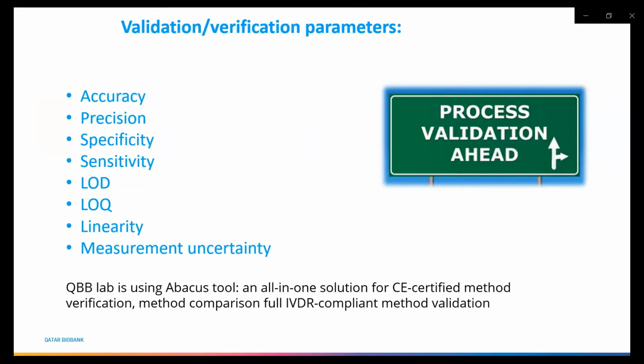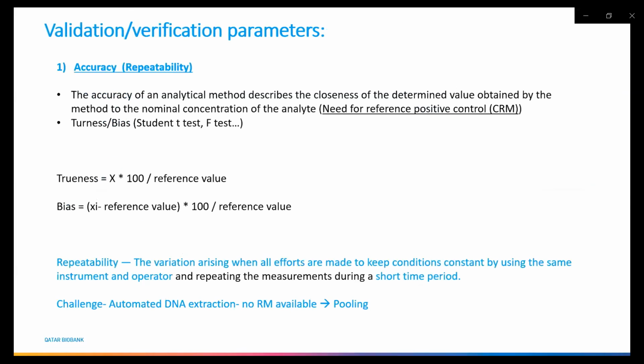validated. To perform a validation or verification, there are parameters that have to be followed: accuracy, precision, specificity, sensitivity, limit of detection, limit of quantification, linearity, and measurement uncertainty. Here in the Biobank, we are using a great Excel add-in, the Abacus tool, which is CE certified, easily applied, and avoids human error during the stringent and complicated statistical analysis.